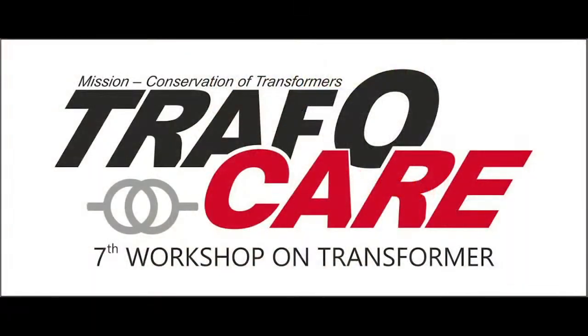Whereas in the case of 400 kV by 220 kV, though it is possible to provide the tap changer on the neutral, as per the specification prevailing in India, we are providing the tap changer mostly on the line end of 220 kV. And that is where the challenge lies. So if we transition to a tap changer on the neutral of a 400 kV by 220 kV, most of the challenges, the risks or apprehensions people have on the OLTC, can move away. This is my feeling, because we have seen that there are countries using 400 kV by 220 kV ICTs with the tap changer on the neutral end.